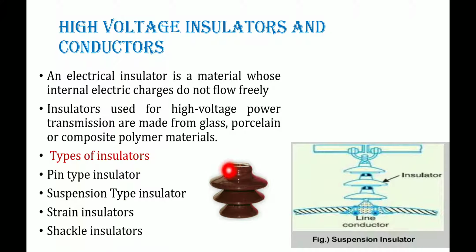As the voltage goes up to 33 kV, this kind of pin type insulator is used. When the voltage increases beyond 33 kV, it becomes more uneconomical to use pin type insulators, because the size and weight of insulators increase, making handling and replacing quite difficult. So to overcome these difficulties, instead of pin insulators, suspension type insulator was developed.